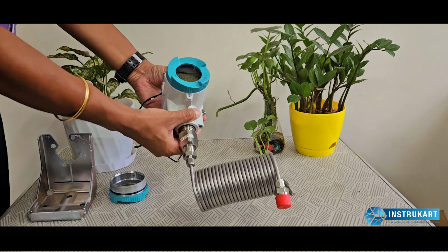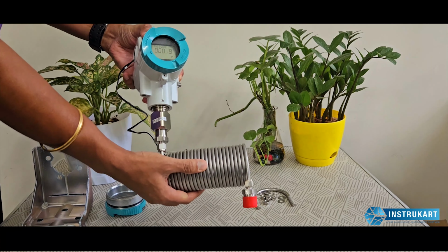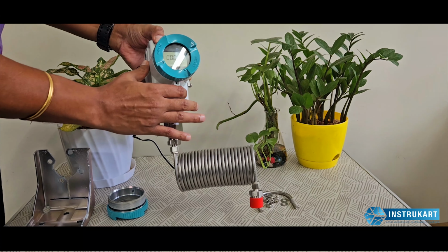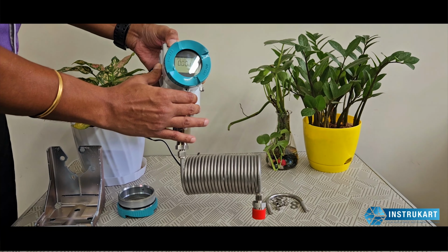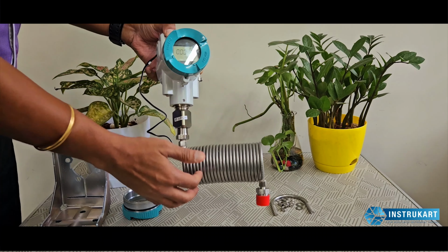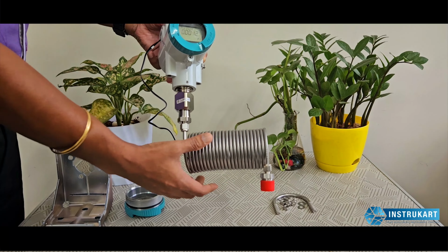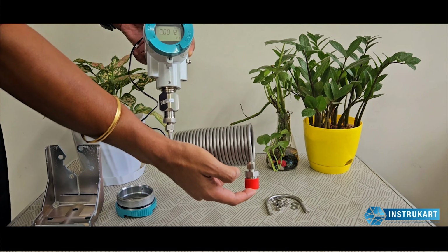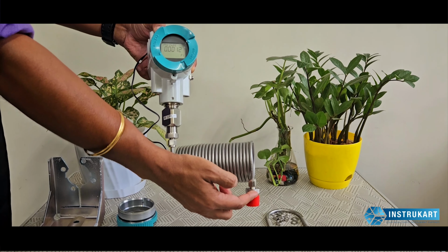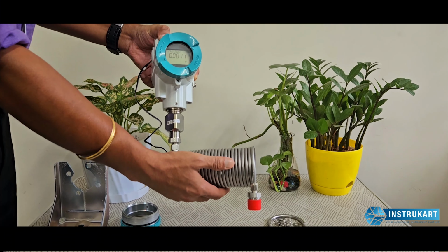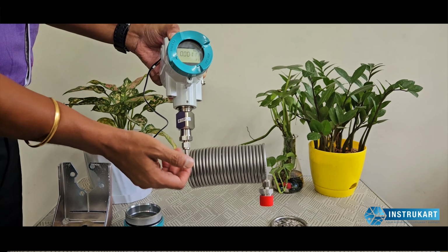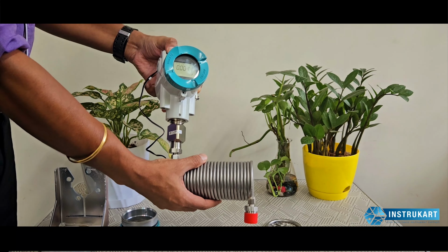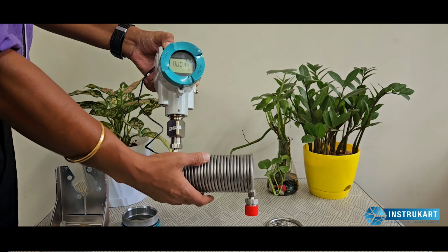So in some scenarios what happens is that the line temperature would be higher and the temperature which this particular pressure transmitter can take will be lower. So in these cases we use the cooling coil. This is the cooling coil which is fixed along with this pressure transmitter, where one side is for the process, which means that at this point the temperature would be more than 400, 500, 600 degrees, which has to be further reduced to 150 degrees, which this particular pressure transmitter can take. Hence these cooling coils are used, or we can use siphons also to reduce the temperature.